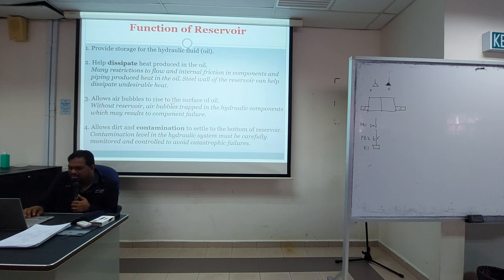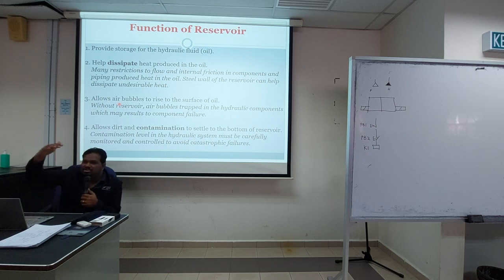Okay, allow air bubble to rise to the surface of oil. So dia ada mechanism, sebab kalau ada air bubble, so what will happen? The air bubble will cause the systems to start, valve untuk start ataupun hydraulic. So it can cause a lot of damage to the machine. So air bubble ni you perlu keluarkan. So without reservoir, air bubble trapped in the hydraulic component may result in component failure. So kita nak ada satu mechanism untuk remove the air bubble. So you can make the air bubble to come to the surface. So dia sampai ke surface, air bubble tu dia akan keluarlah ke environment.